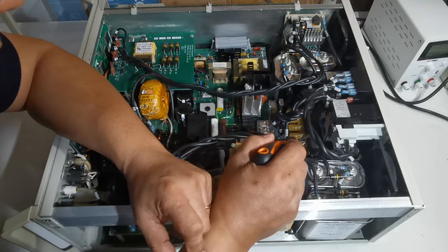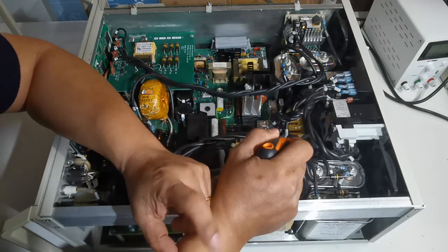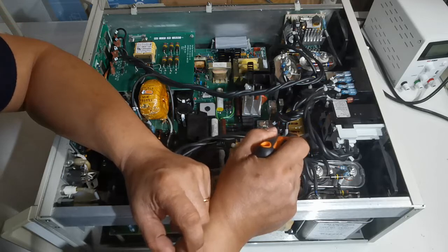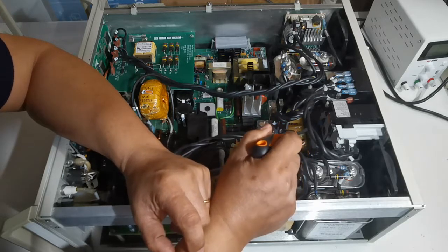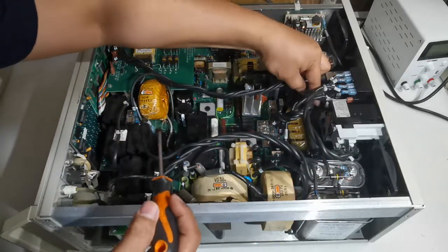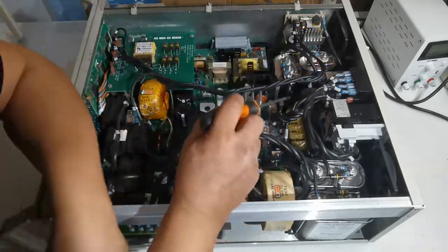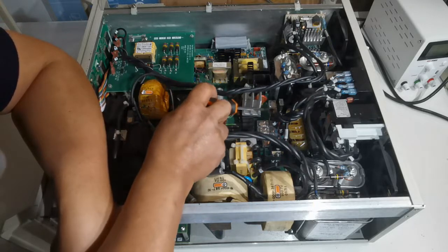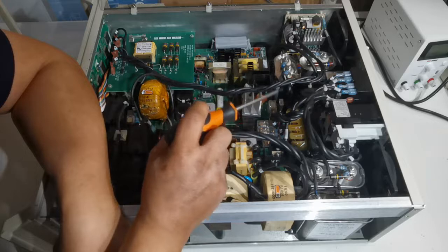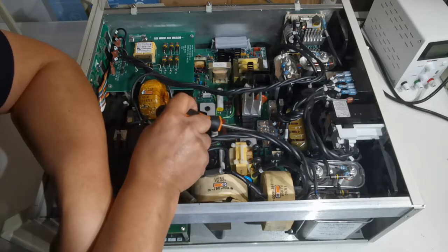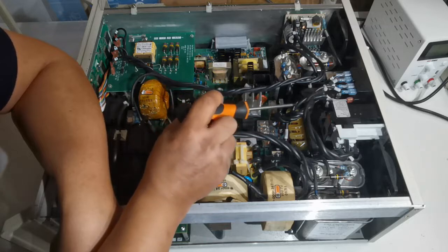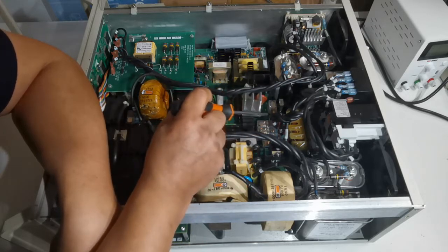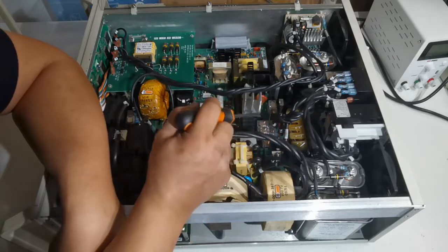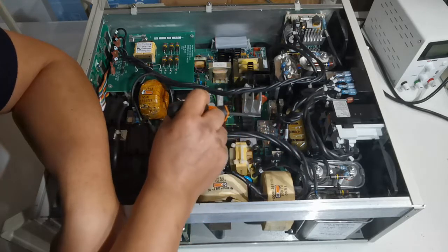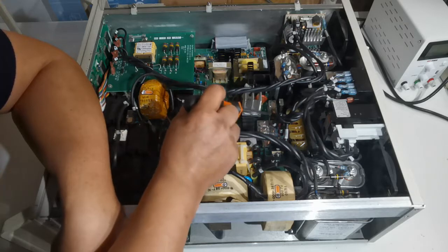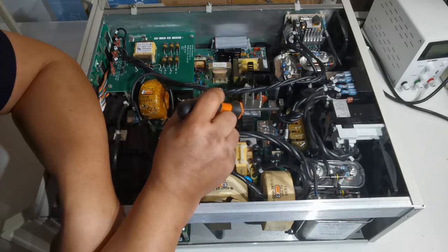has 80%, 40%. There's also 70%. This is mainly used for voltage dips and interruptions. And the tap is selected, connected through, so you can see that the transformer is connected to this board here, which is through relays. This relay will select which tap when you apply a voltage dip interruption or the PQF. This relay will activate depending on which tap of the transformer is selected.